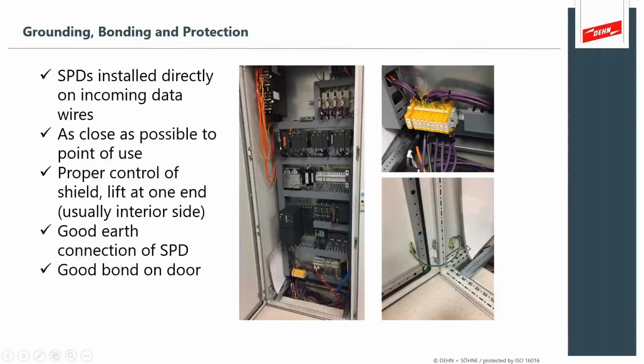And there's plenty of applications where you'll get a chance to see this bond correctly installed. You'll be looking for the similar master bar inside of your cabinet. You're looking for single point of earth, something that you hear the term star bond. But what's important is that you're looking for a good solid earthing system to supplement and take care of the electrical operation.